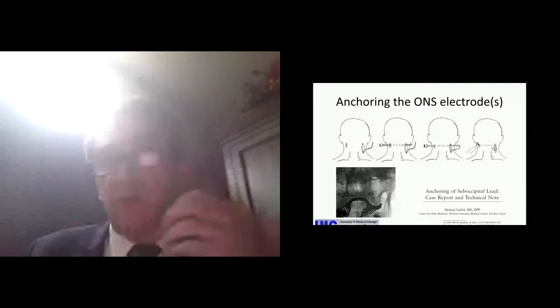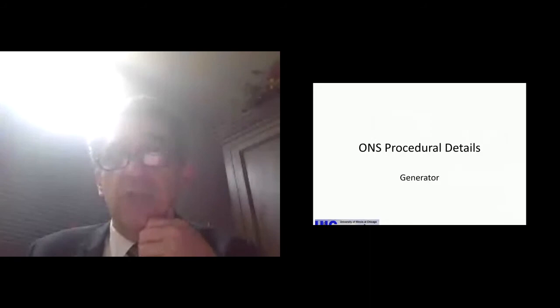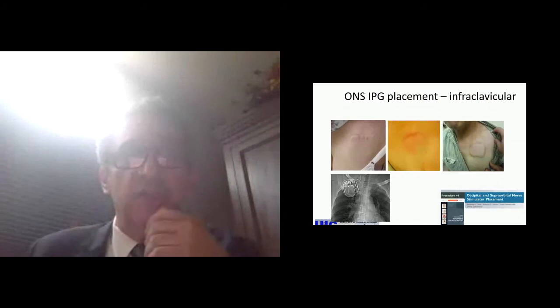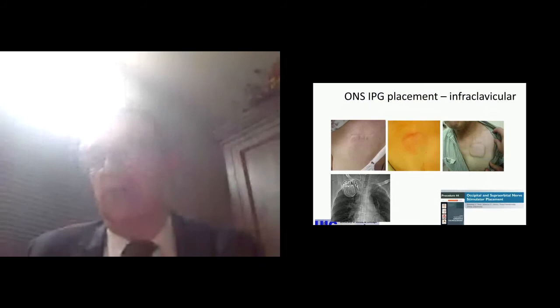The generator and most electrodes that we use now are still requiring a generator, which is a power source, even though there's some new technology that allows you to use this stimulation without generators. But a generator is like a pacemaker essentially—something that delivers energy to the electrodes. There were some publications recommending putting generator all the way to the flank or the buttock. I don't do that. I put my generators in the chest like I do with vagal nerve stimulation or deep brain stimulation devices. As a matter of fact, if the patient has a nice tattoo there, then you can make the generator look like a pedestal for this. This is something that we use routinely, and we surveyed our patients and it turns out that most of them would prefer that location for their stimulation devices. And then there's a technique of how to position the patient—something that probably has more relevance to surgeons who do that—but there's a way to do this in a safe and effective way when you position the patient and get access to both sides of midline and the generator in the same approach, so you don't have to re-drape the patient and reposition them during the surgery.